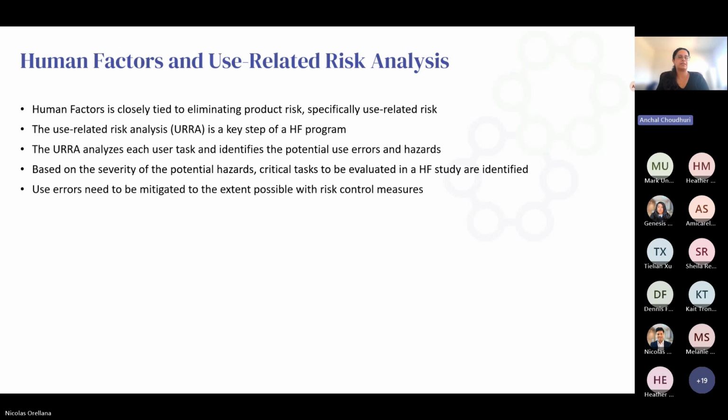And really the only times you see that a human factors study isn't needed when critical tasks are identified is if trained medical professionals are the only users, and the design of the product is something that's very commonly used, and hasn't really changed too much from something that's already on the market.